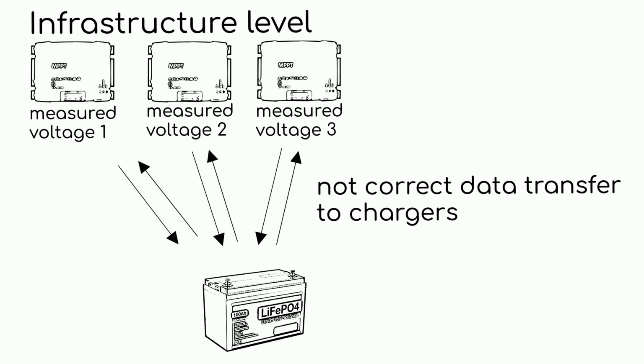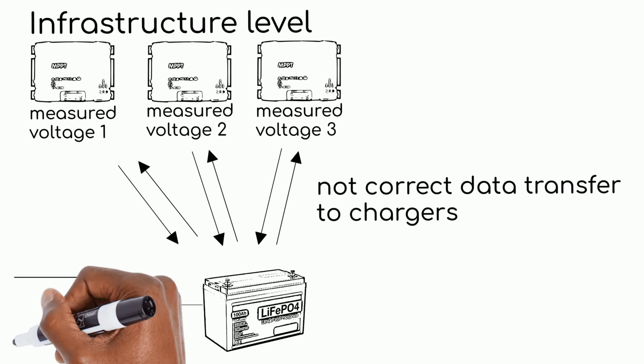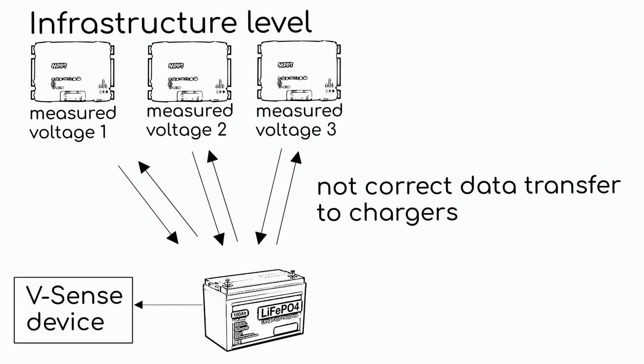Knowing about the losses in the wires, we can make adjustments to the charger settings. But this is not the right option. Since charging currents from alternative energy sources may be different, the losses will also be different. To solve the problem, so-called VSense devices are added to the infrastructure. Typically, a VSense device is a device connected directly to the battery. The task of the device is to measure the real voltage and transmit the value directly to the charger. Knowing the actual battery voltage, the charger adjusts the output voltage.